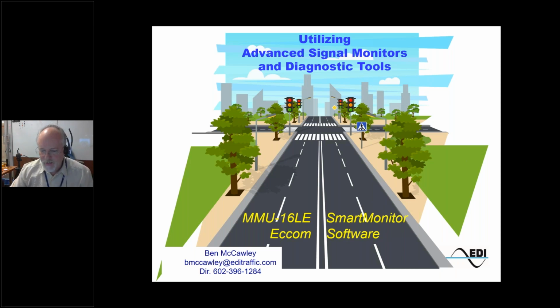If you don't do that and you just change it, your intersection may go on the flash, or it may not even come out of flash because it's confused. It's like, wait, you have something queued up here, but I don't know which is what. So what do you want? Pushing and holding the reset will tell the monitor, hey, we're starting fresh, everything's good, let's go. Does that make sense? It does.